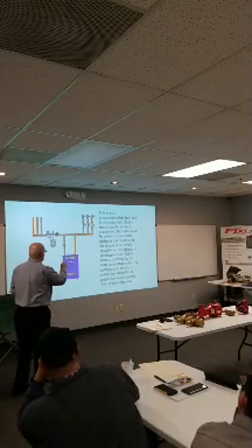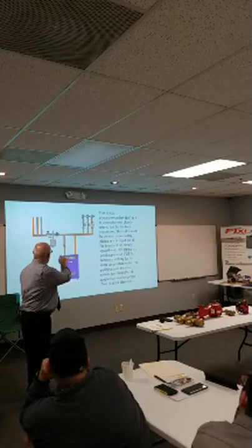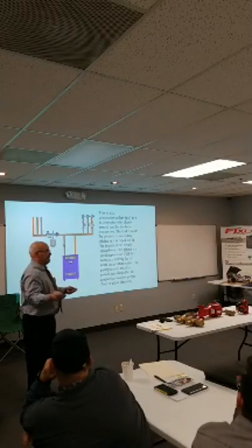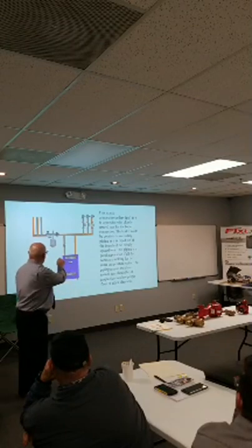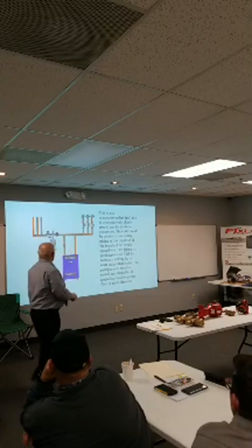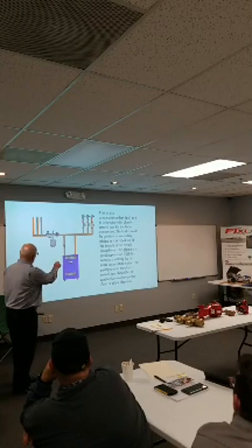Okay, do primary, secondary on the boiler loop, and then this supply manifold is all the same temperature all the time, because I'm not tempering it over here. So you've got what, a control valve and a balancing valve? That's a zone valve, and this is my system pump. And then this is another pump in here.